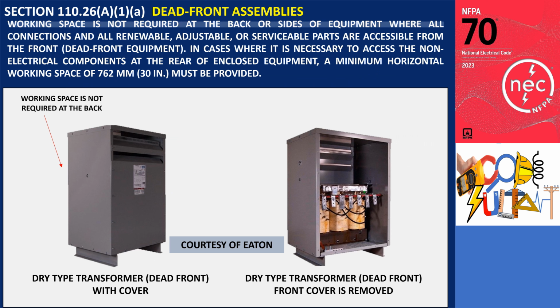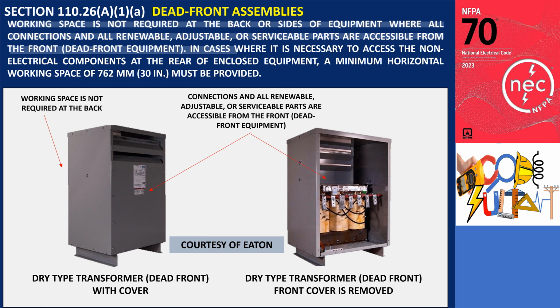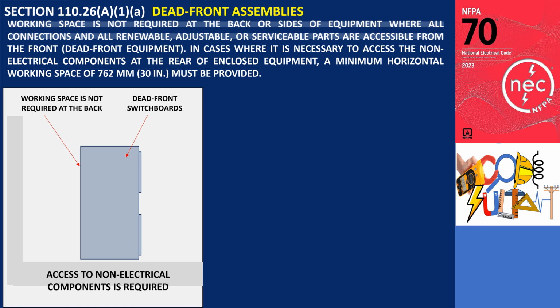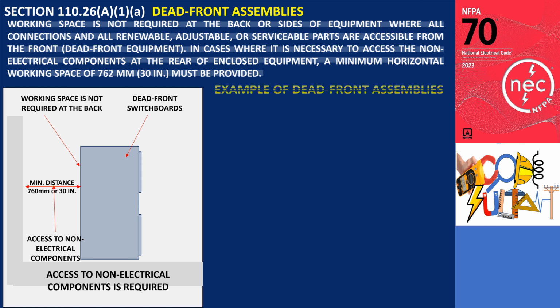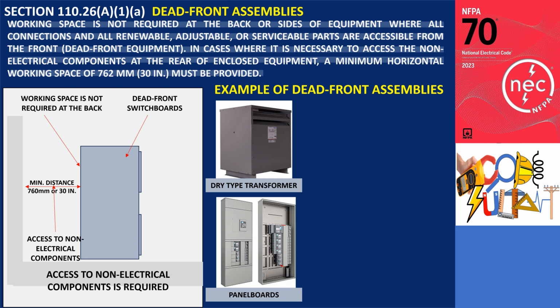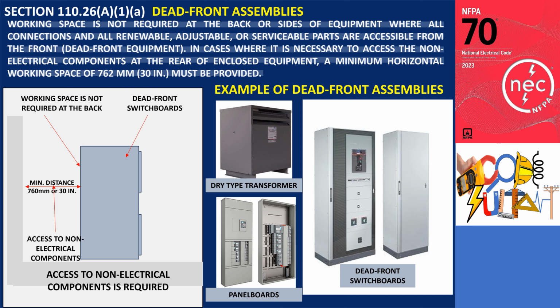Working space is not required at the back or sides of equipment where all connections and all renewable, adjustable, or serviceable parts are accessible from the front, dead front equipment, as stated in subsection 110.26(A)(1)(a). In cases where it is necessary to access the non-electrical components at the rear of enclosed equipment, a minimum horizontal working space of 762 millimeters, 30 inches, must be provided. An example of these are dead front dry-type transformers, panel boards, and dead front switchboards where all the connections and renewable or adjustable parts are accessible from locations other than the back or sides. There is no working space required for the back or sides of the equipment.